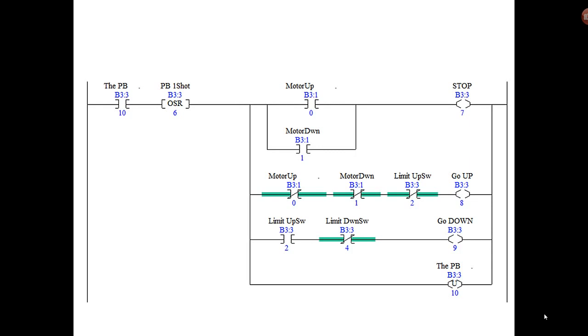A one-shot instruction is true for one program scan, which means if everything to the left is true, the first scan that is true the instruction is true and then the rest of the rung is executed. However, on the next scan, everything to the left might still be true but it's already been true for one scan, so the OSR instruction is now false and the rest of the rung is false.